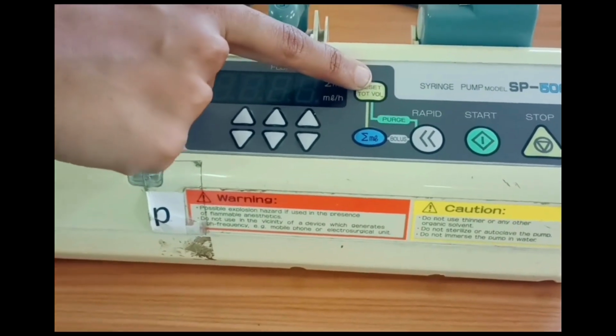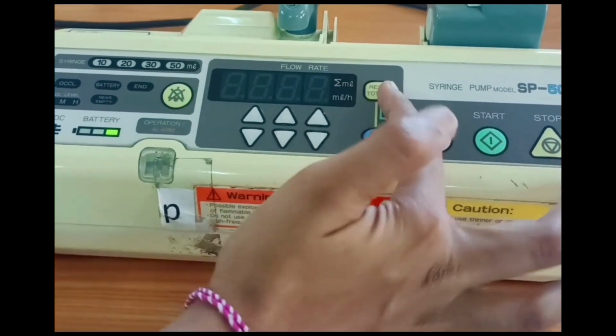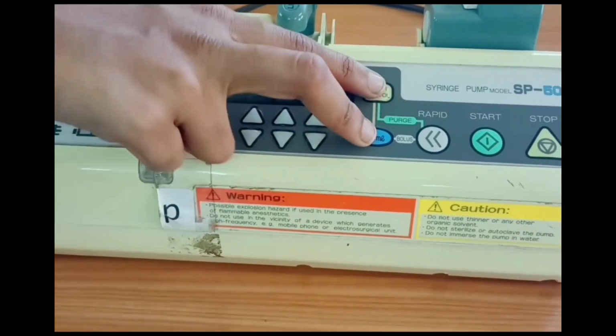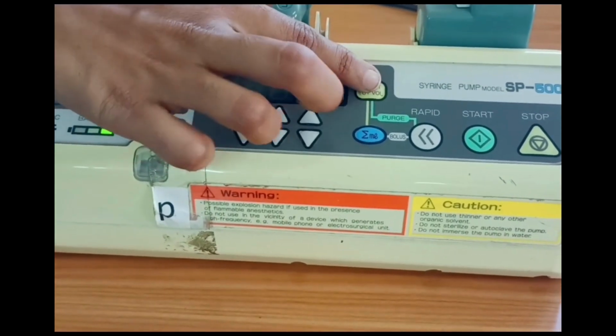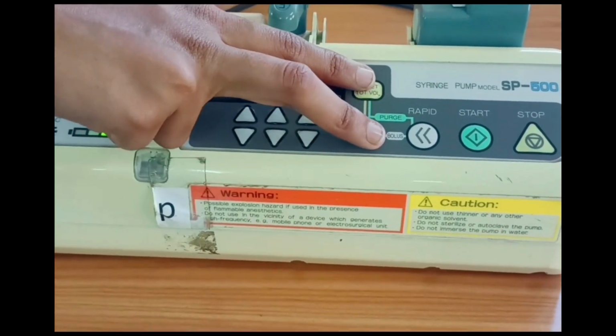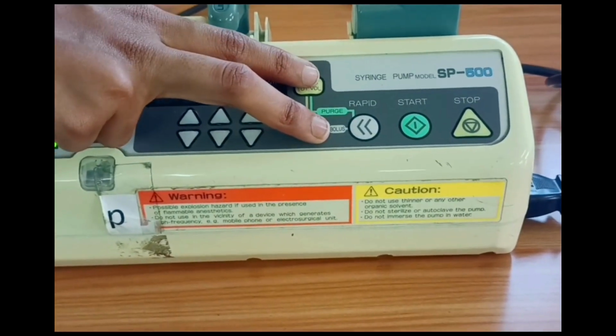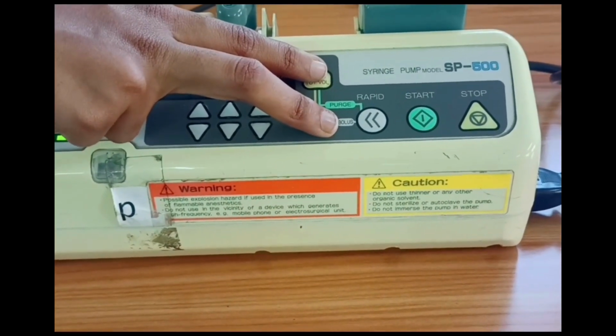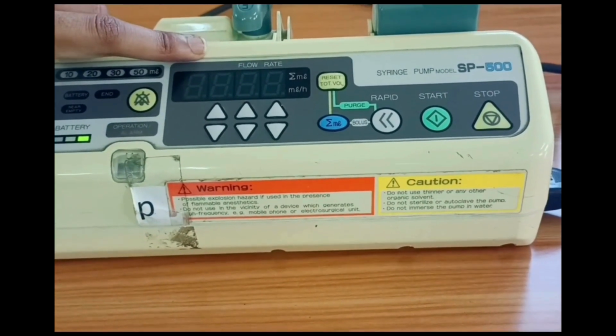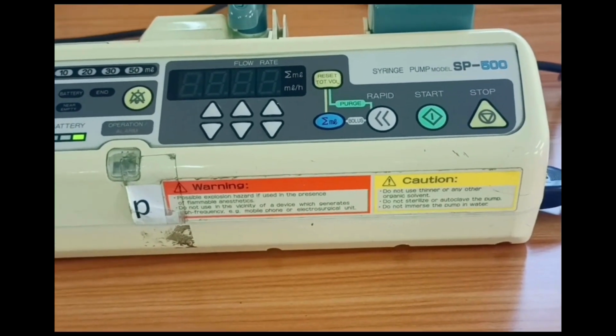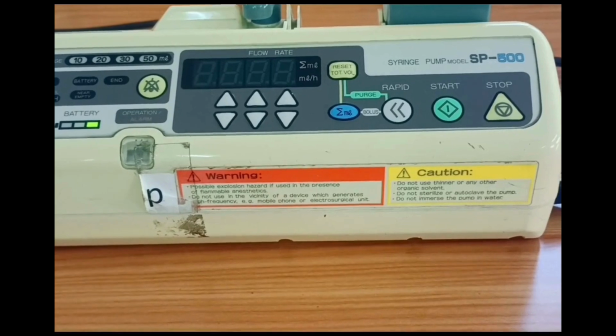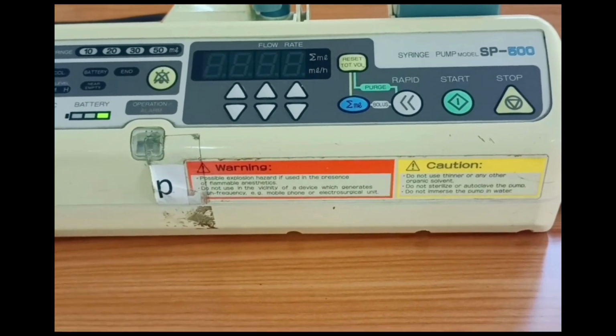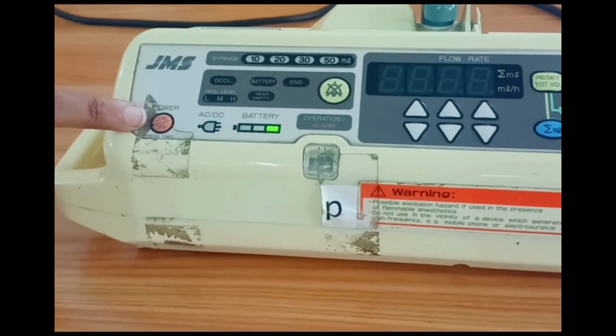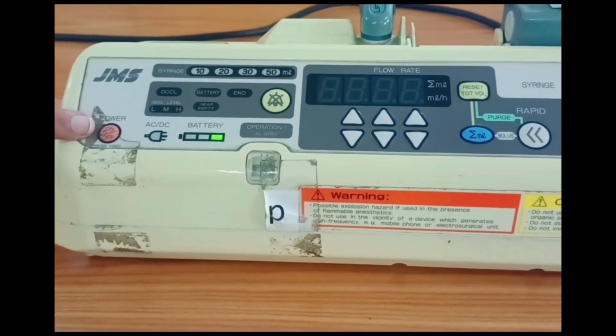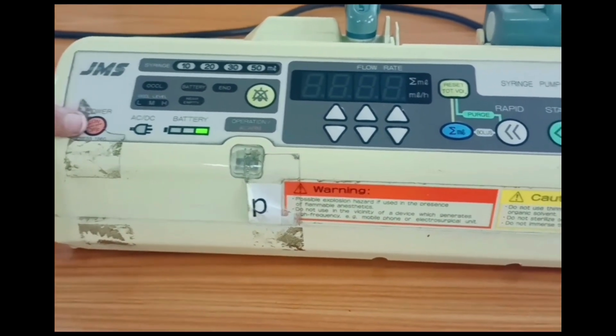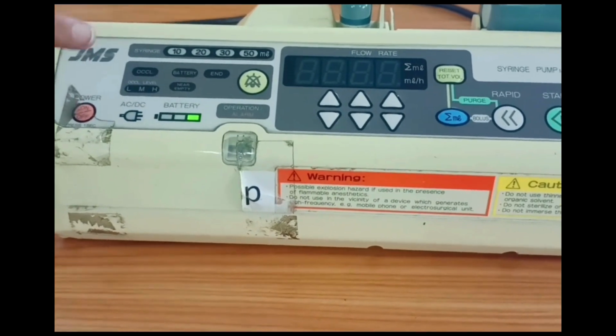Press the switch together with ML. If you press the reset total volume switch and the ML switch together, the total volume delivered is reset to 0. Press this switch twice together with the rapid switch to purge the line. This volume of purging is added to the total volume. Power switch. This is the power switch. This switch turns the power on or off. Press this switch continuously for 1 second to turn the power on or off.